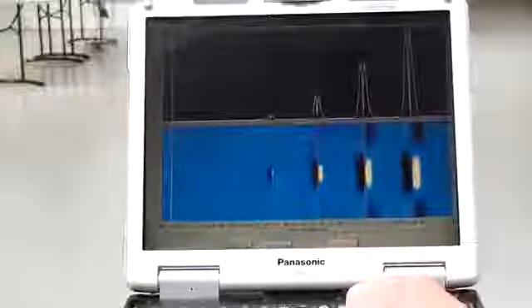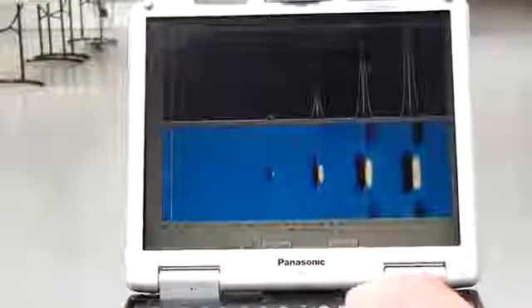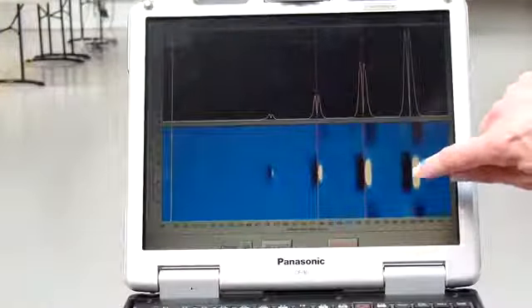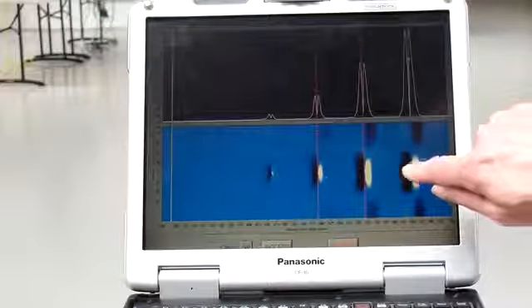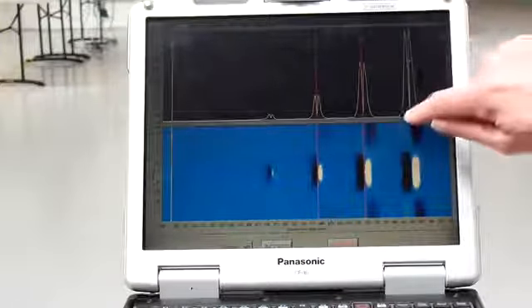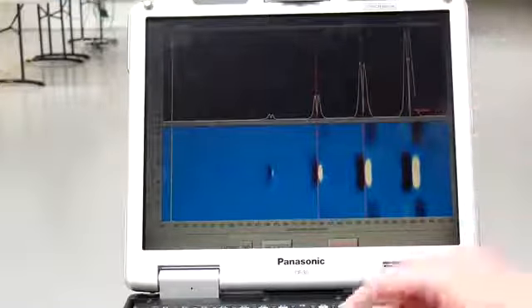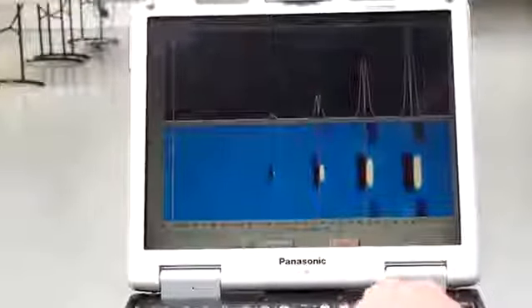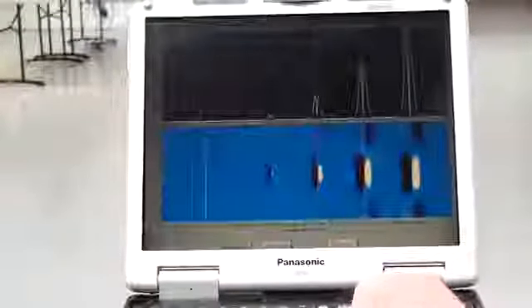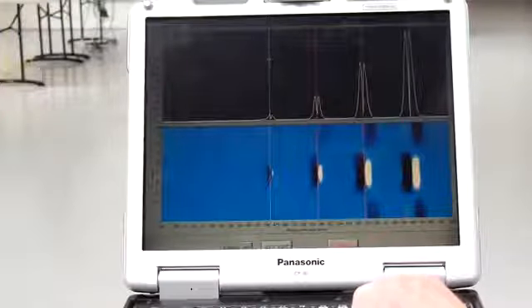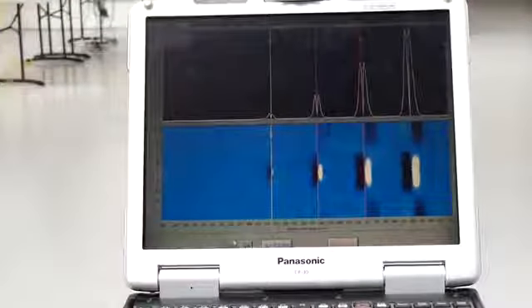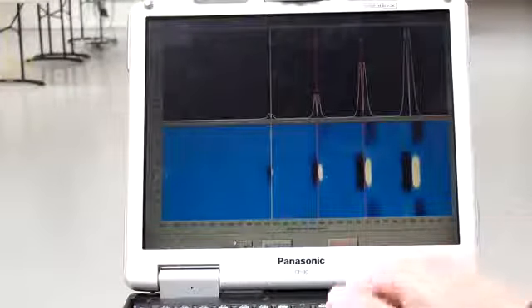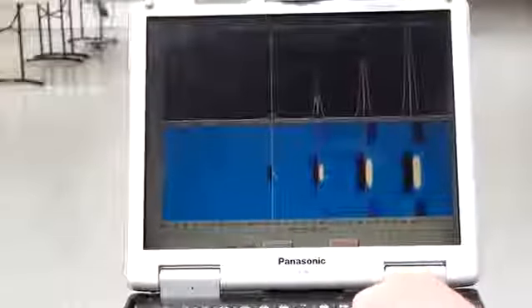The 80% gate is the purple one, positioned here. It's important that the gate is aligned with the phase change of the signal between the black and the white regions on the C scan and at the central minima on the A scan. I will now position the 20% cursor by clicking the mouse and dragging it into position like so. With the cursors in place on the indications, we press the accept button to accept the calibration.